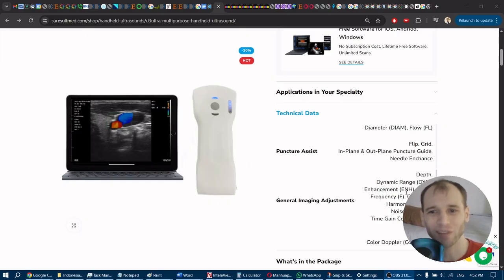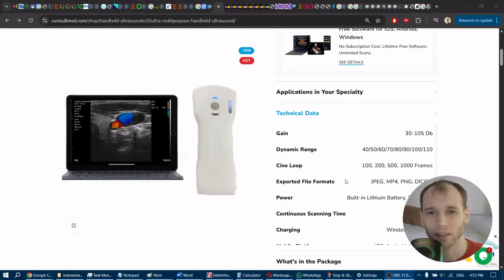But there's set values. I can't set the frequency to everything I want. It's only the two presets. The focus, you just press the focus and it cycles through pre-selected focus points. So you can't move the focus to exactly where you want. So there are limitations to how you can adjust the image. But that being said, you can adjust the image, which is nice. And this is great.